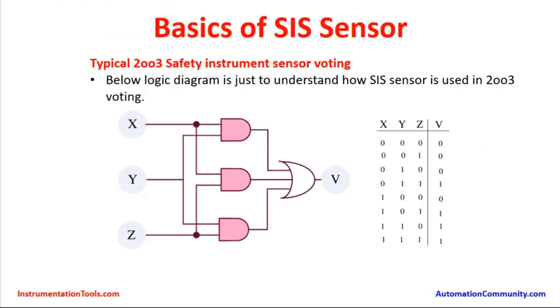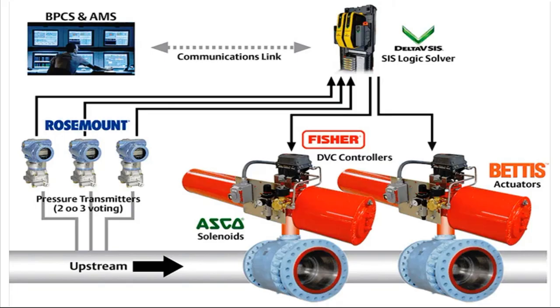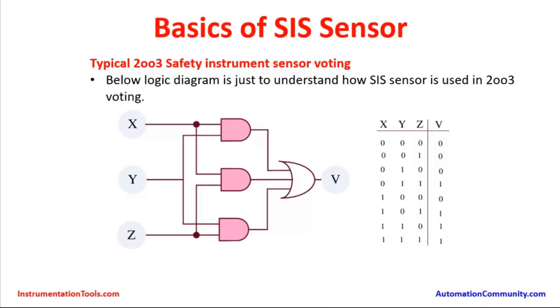Different kinds of measurements will have three different sensors on the same process line to ensure that two out of three sensors going to high level, high pressure, or high temperature triggers a safety action. This is to ensure there is no spurious tripping whenever a particular instrument fails. Just to ensure instrument reliability is quite high for the safe operation of the plants. This is a small truth table — those familiar with electronics or instrumentation should be aware of AND gates and OR gates.